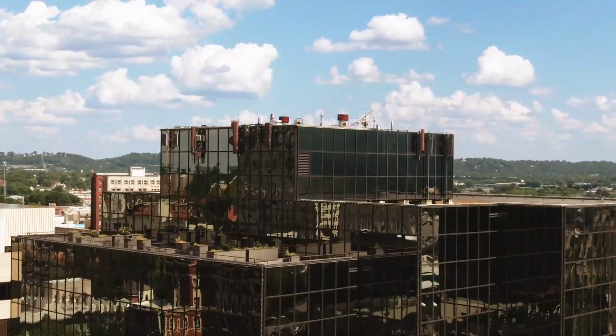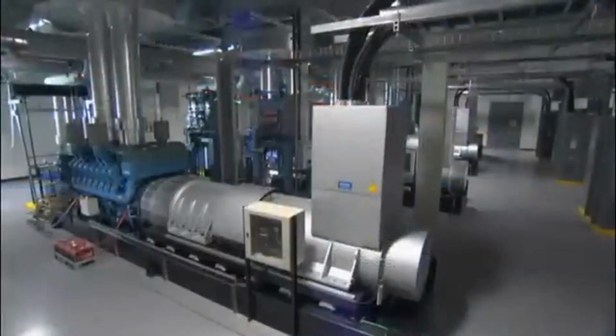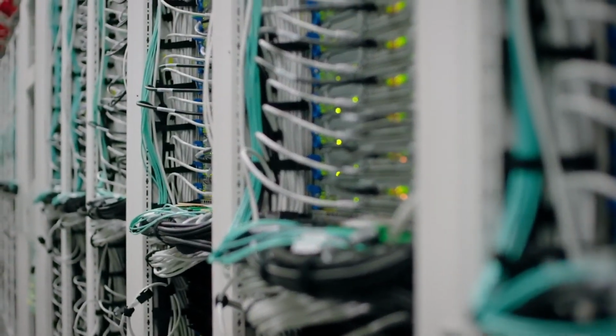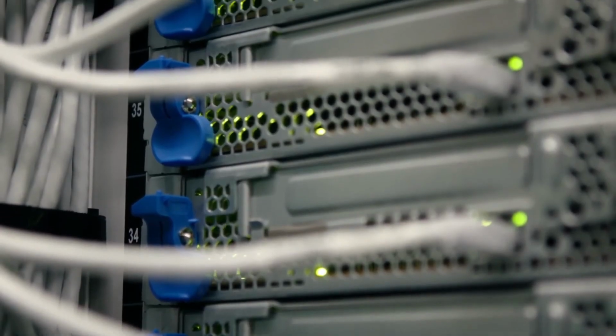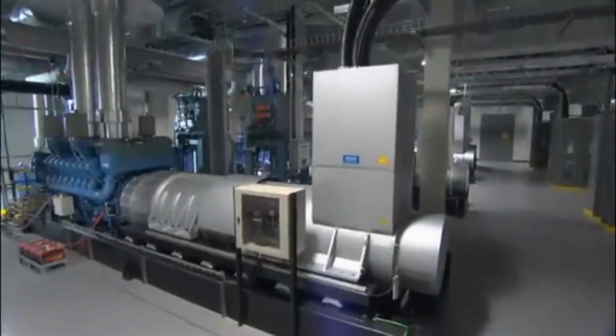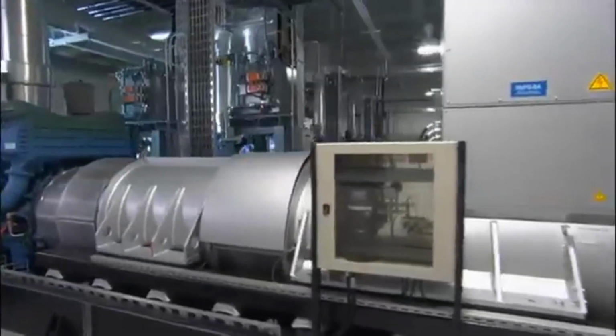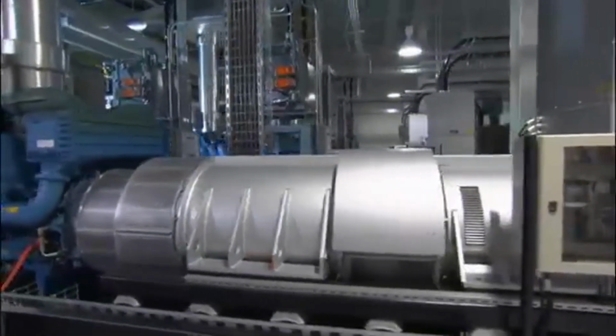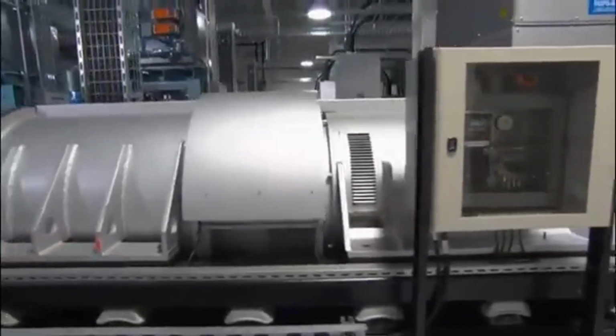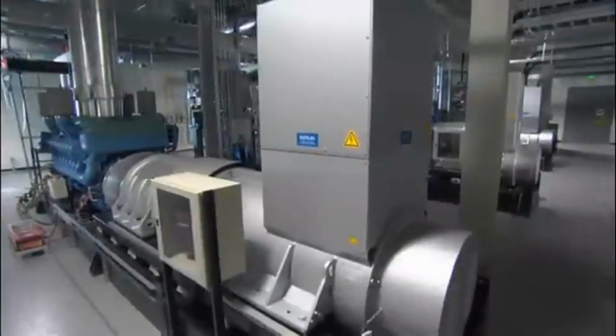Data centers just said, nope, we are out, and flipped to generators and UPSs. Because remember, data center loads are crazy sensitive to voltage dips. And if a series of faults happen in a short period of time, the backup systems at many data centers do not automatically switch from UPS back to the main grid and have to be changed manually. Here as well, data centers' load did not return to the grid for hours.